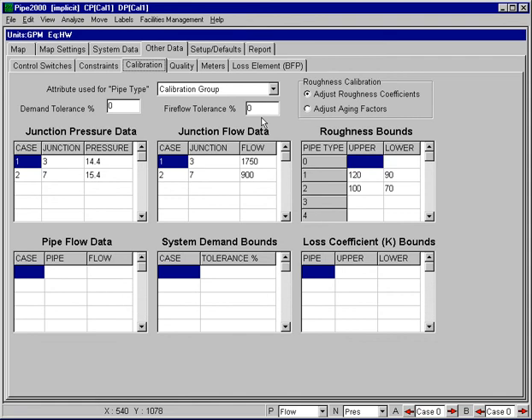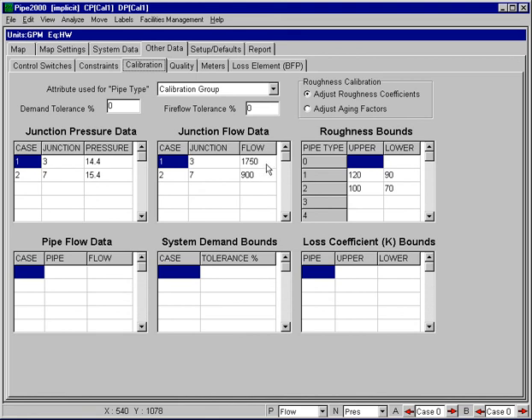Again, when a non-zero value is specified, the calibration algorithm will attempt to make adjustments within this specified tolerance to any of these fire flow values that we've specified. And again, we'll try to do that to improve on our calibration. Implicit in an assignment of this number is that there is some variability or potential error, perhaps, in the observations that you've collected in the field with regard to these fire flows. And with this cell, you can explicitly take that into consideration.